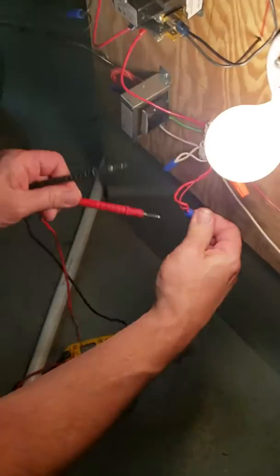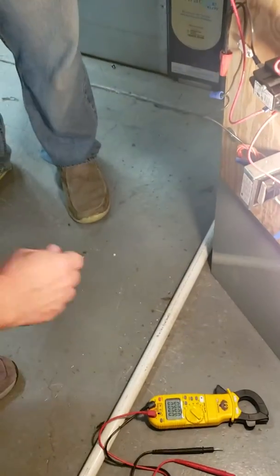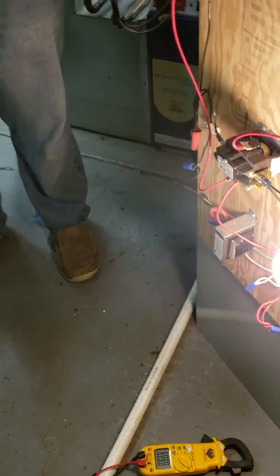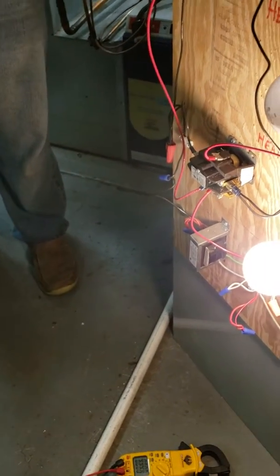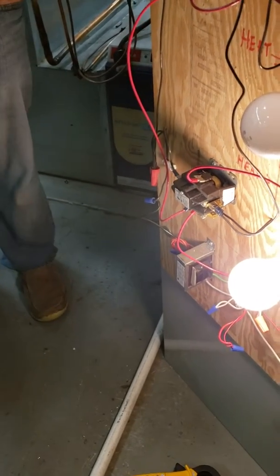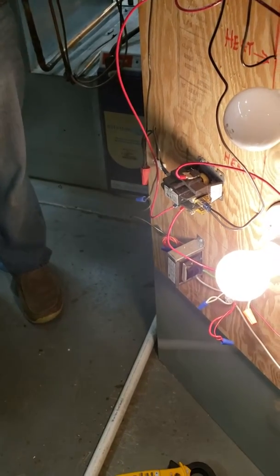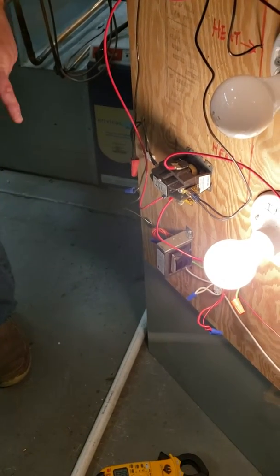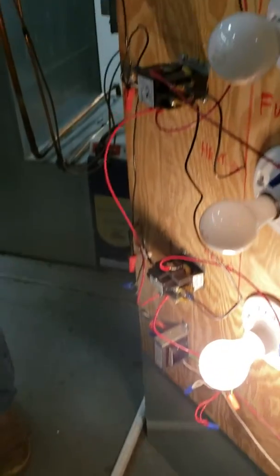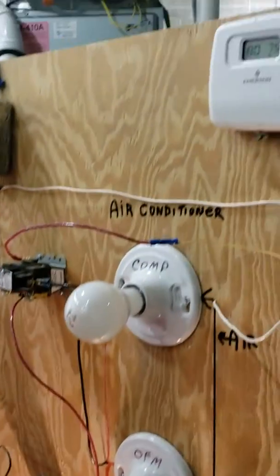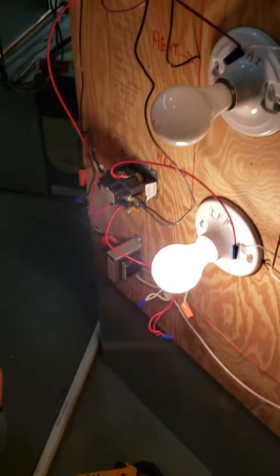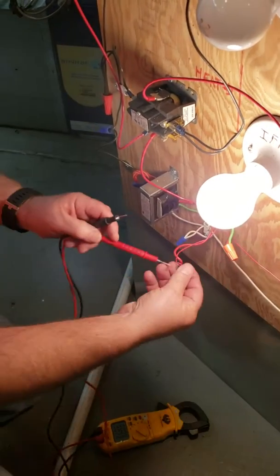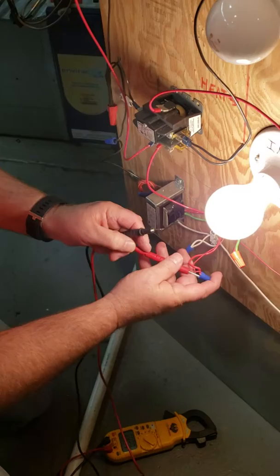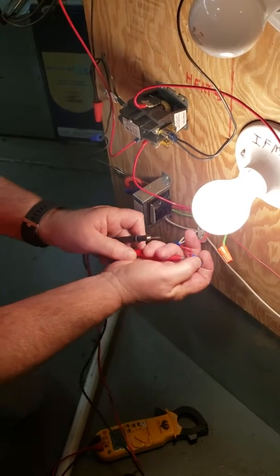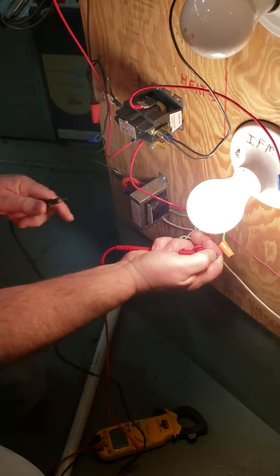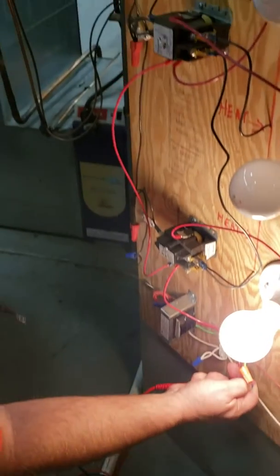So I know I must have input on my transformer. So what's going on? Something's up with the relay, right? Yeah. So if I've got power feeding that red wire up to my thermostat. So here's the next thing I'm gonna do. Where's my red one? Here it is. So I'm feeding up to my thermostat. Then coming out of the thermostat to feed cooling, it's coming out of what wire?